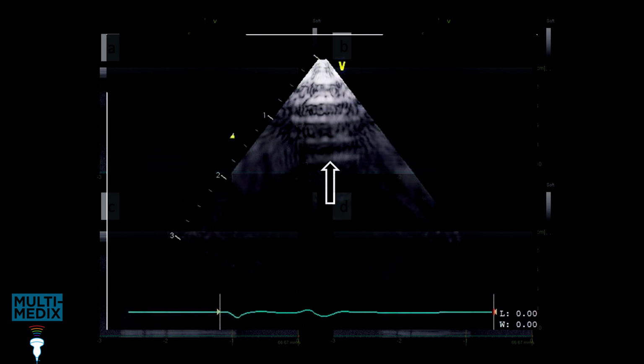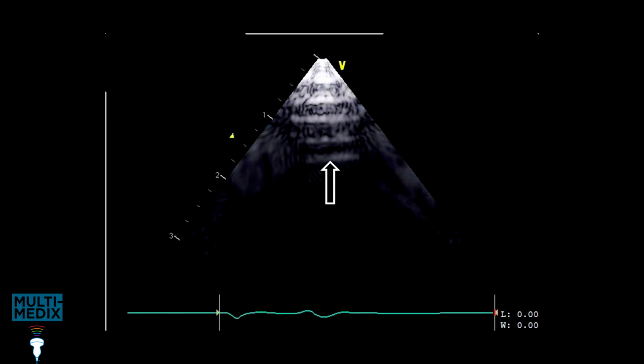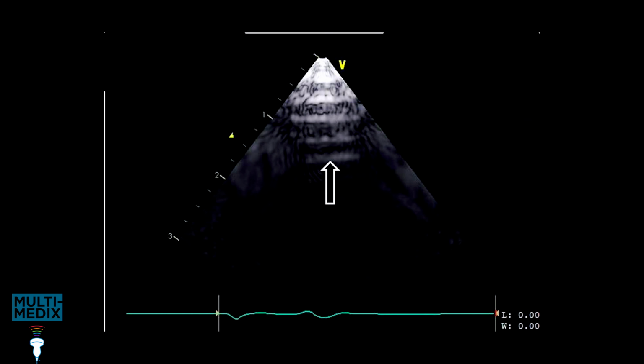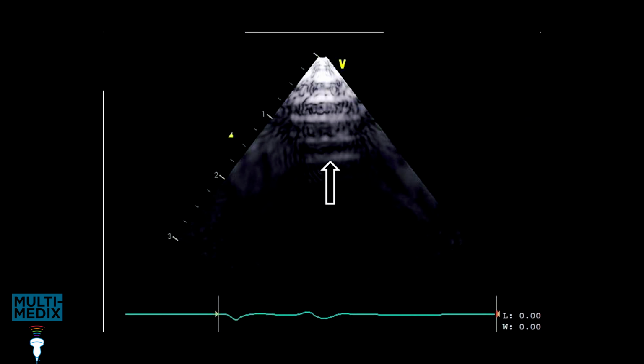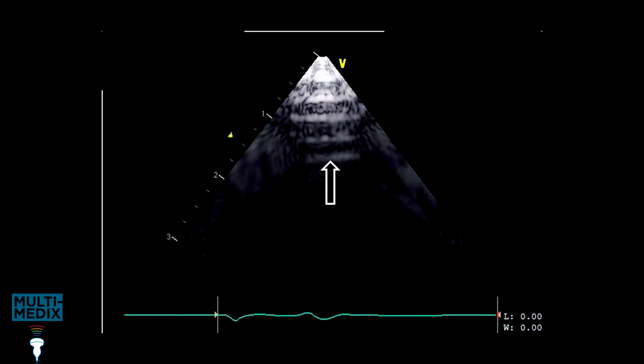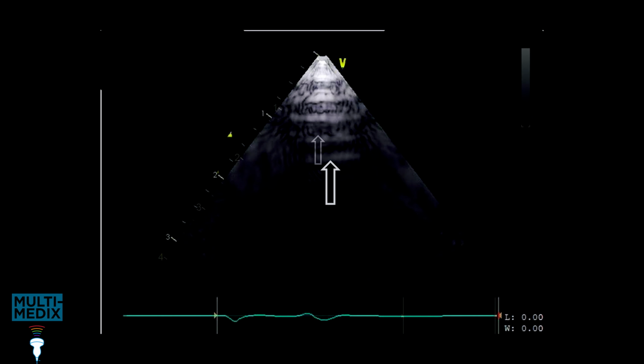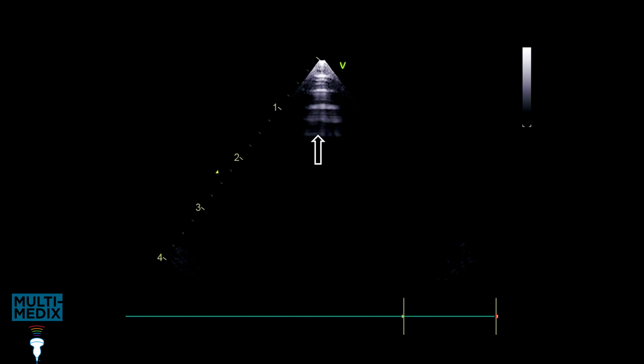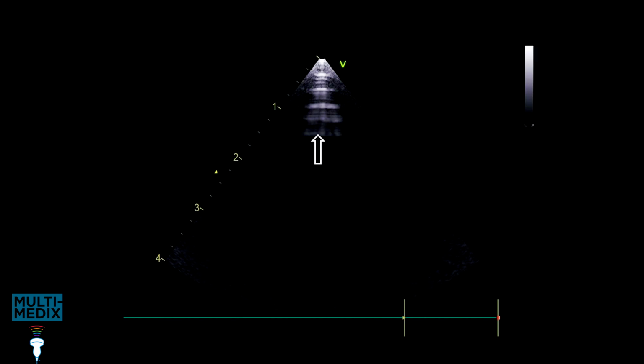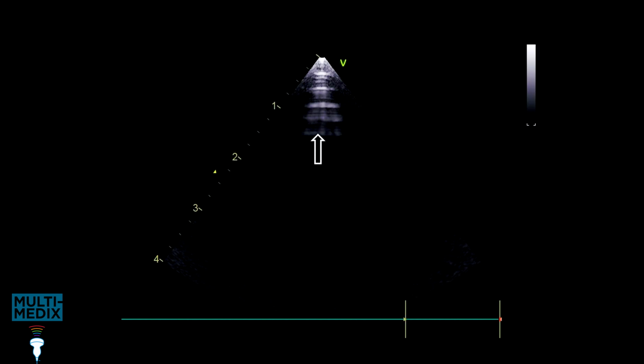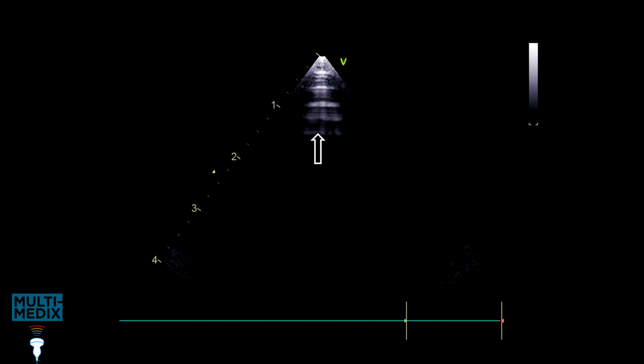The next test is sensitivity assessment. You should use the user QA preset. Make a measurement from the top of the image to the deepest reverberation line in the middle third of the image. I apply the rule, if you can see it, measure it. Compare the measurement with the baseline tolerance. If it's inside the tolerance, do the next part of the test. If out of tolerance, it's failed the test.